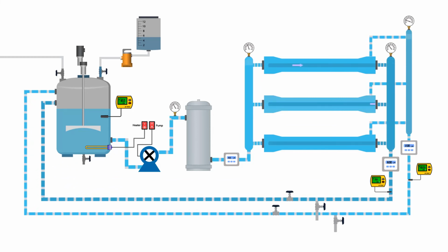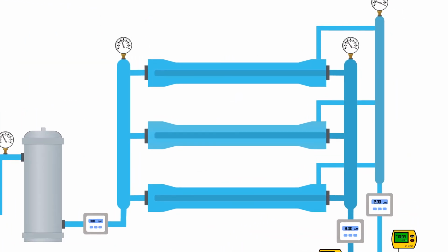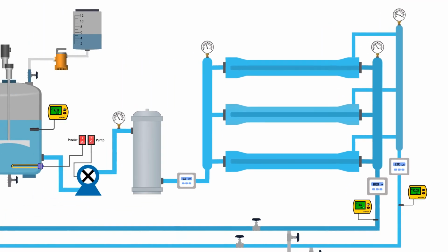Turn off the pump and leave the solution in the membranes for 30 minutes. This allows the solution to react with the microbiological and suspended particles. After 30 minutes, turn on the pump and continue the cleaning process.